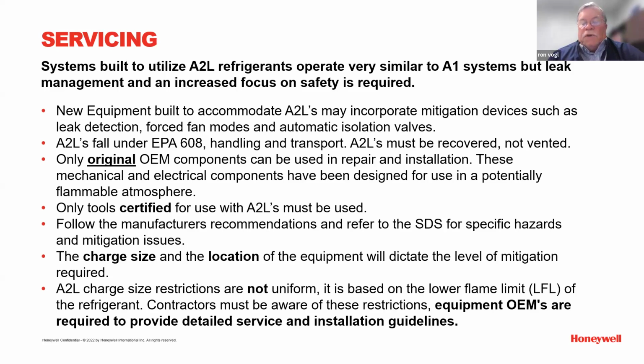So if it calls for a vacuum level, attain it, purge with nitrogen, and be aware of what you're doing. Use equipment specified for A2Ls, it's all out there, I've been surveying all the manufacturers, and I'm sure Johnstone's got it in stock. In servicing this equipment, use only original OEM components. The aftermarket may catch up, but at this point everything on the units will have to be made intrinsically safe, put in different types of enclosures. So only use OEM parts at this point in time.